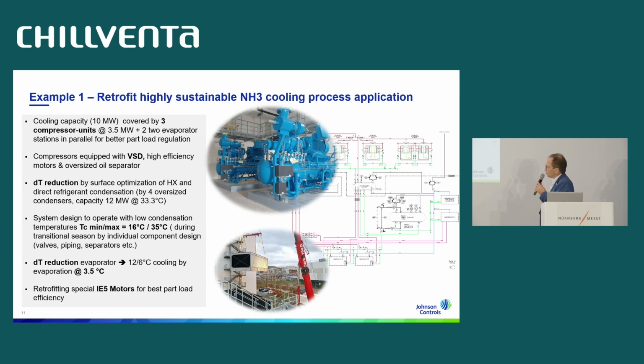And the system was designed to operate even with very low condensation temperatures. During transitional seasons, we have condensation available at 16 degrees by these oversized condensers, which gives you a push in your COP. On the evaporator side, we were also able to reduce the delta T simply by design rules, by oversizing, by having a direct evaporation. So still serving the 12/6 cooling network by evaporation at 3.5 degrees Celsius. So this was a really nice example, running now and saving the customers more than 10% of operating cost per year.